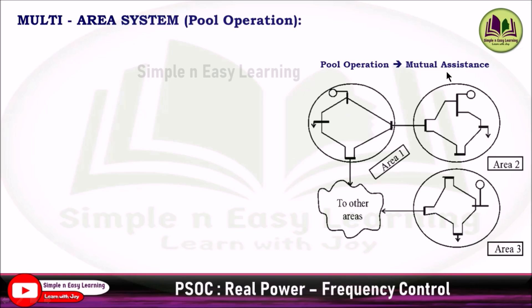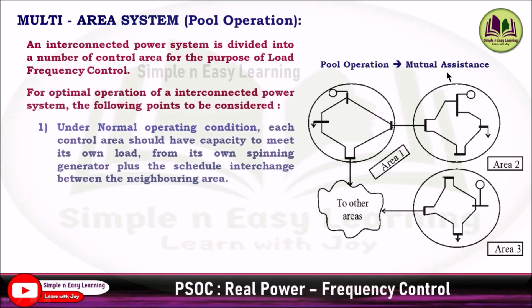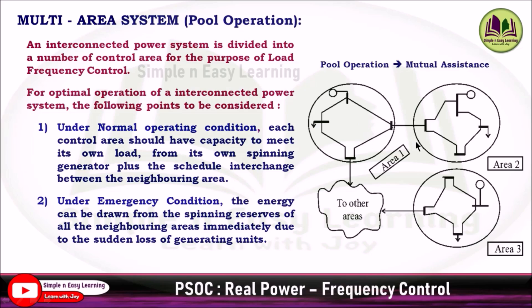Pool operation is a mutual assistance between control areas. They can support nearby control areas in case of any emergency and critical conditions. For optimal operation of an interconnected power system, under normal operating conditions, each control area should have the capacity to meet its own load from its own spinning generators plus the scheduled interchange between neighboring areas. In case of emergency, energy can be drawn from the spinning reserves of all neighboring areas immediately due to sudden loss of generating units.